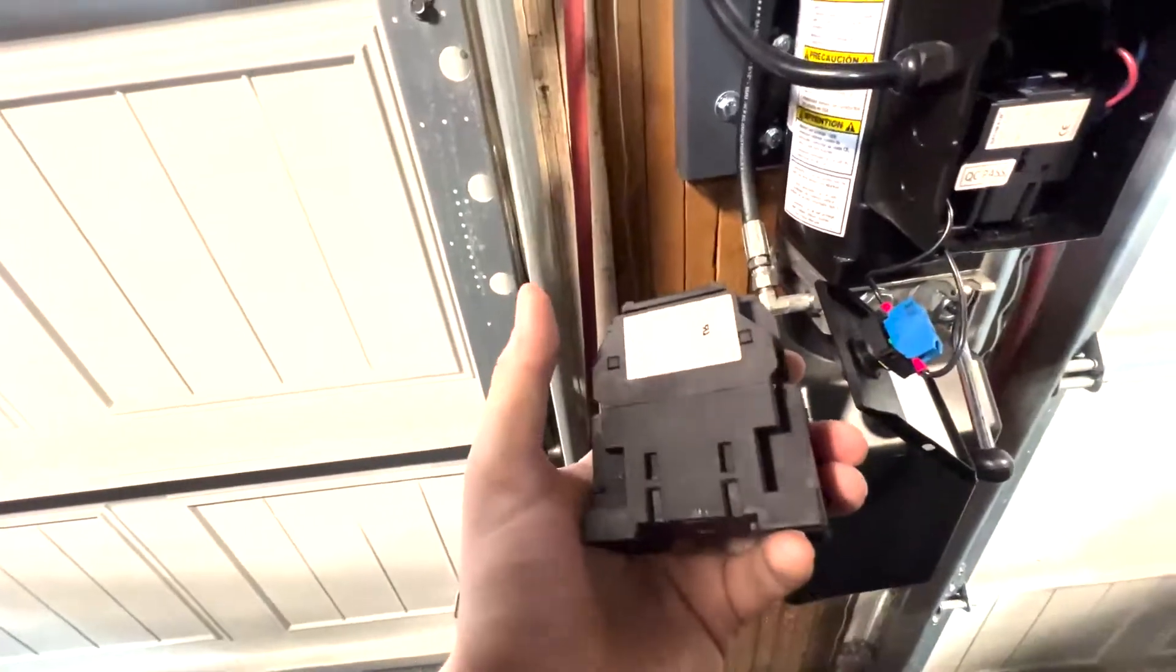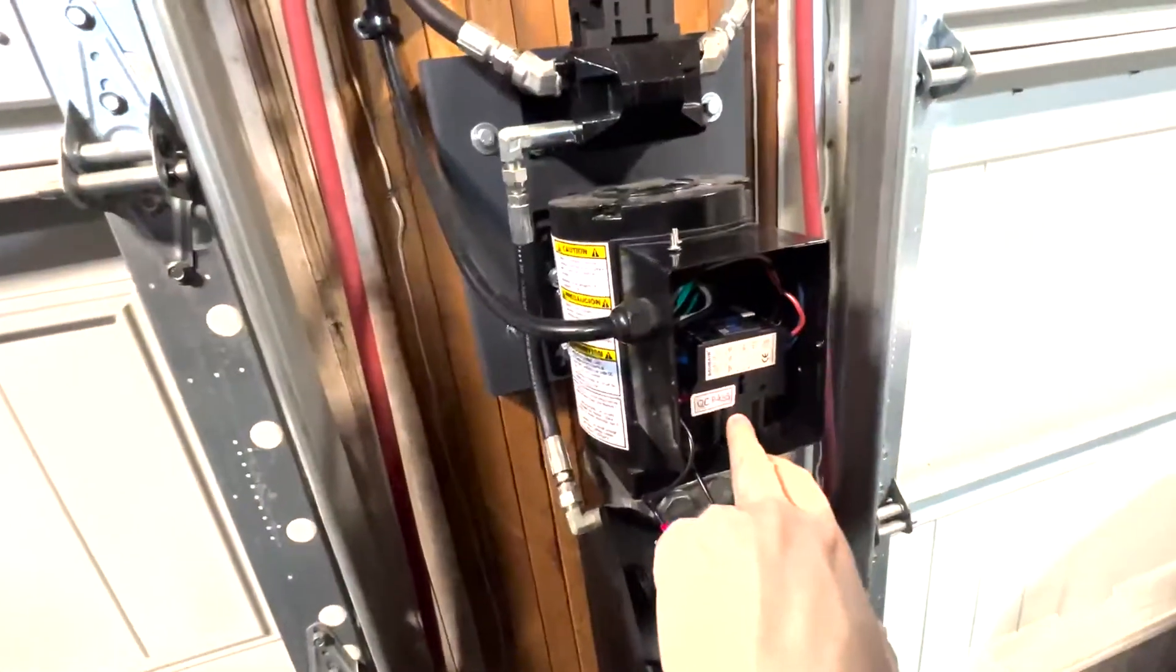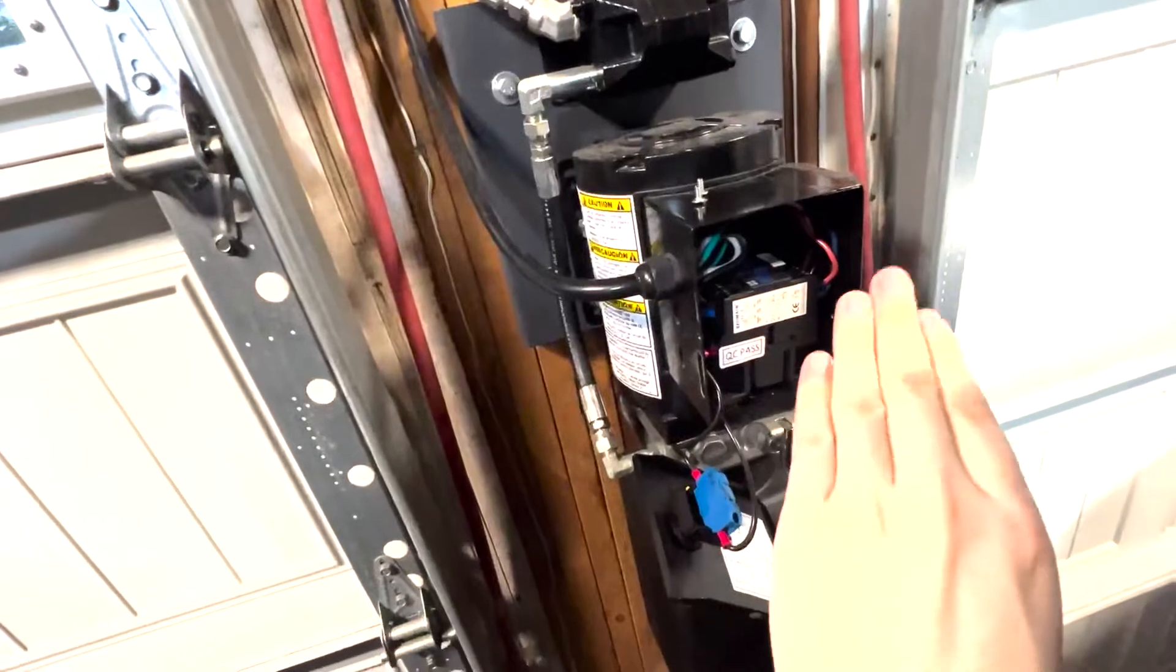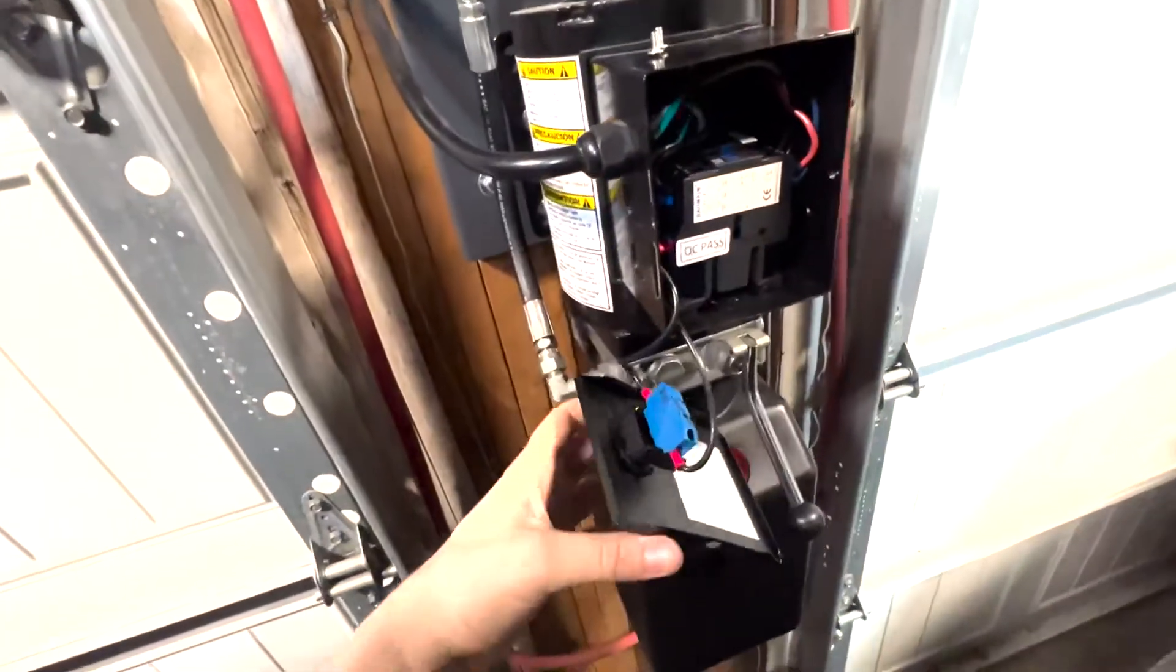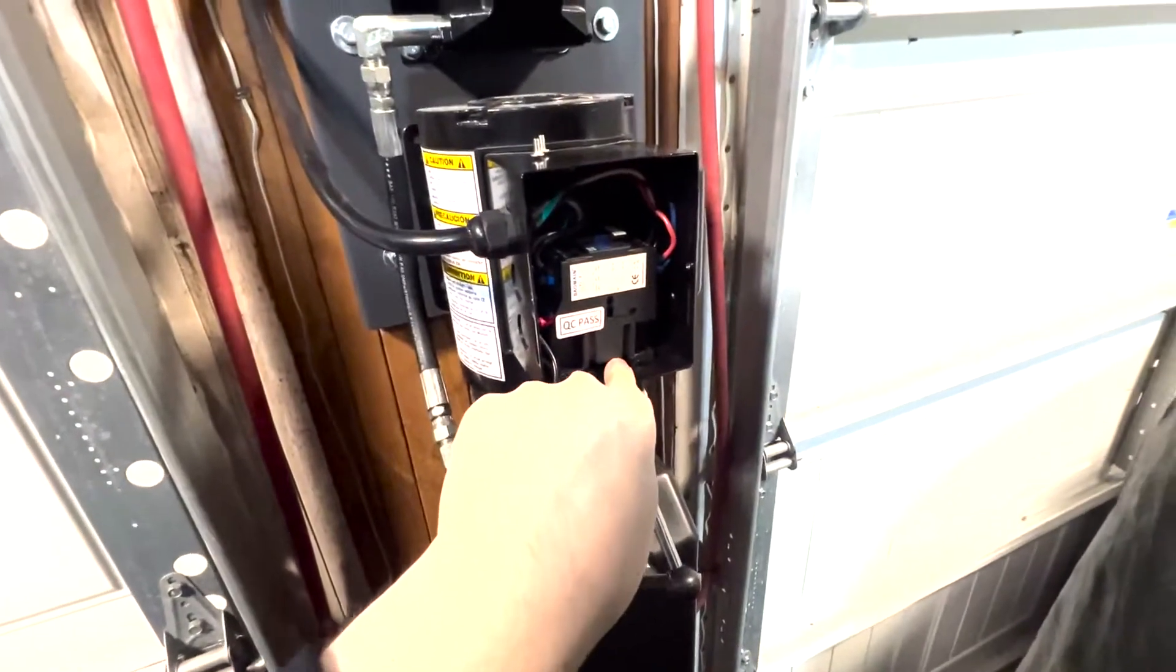But I ran across one day when I was using the lift a lot, I was going up and down quite a few times because I was trying to actually center the rear end in this car, and I found that I smelled like a little burning. I didn't actually smell it at first. The breaker flipped on me first, and then I came over here and was like, okay, why isn't the push button working? I went and flipped the breaker and then I checked up there. I had power and everything was fine, and then I went to open this up and smelled a little burning, obviously unplugging it first.